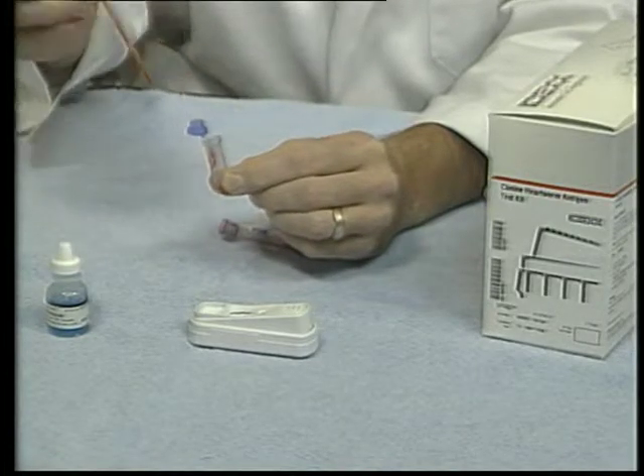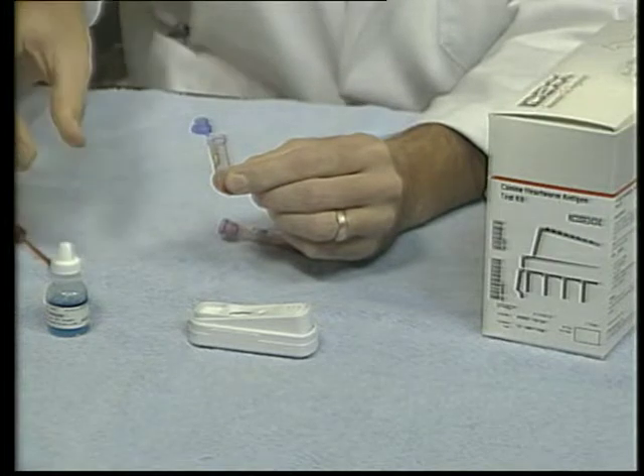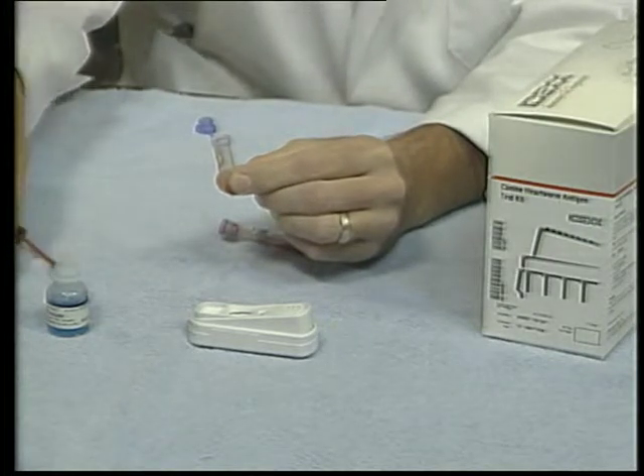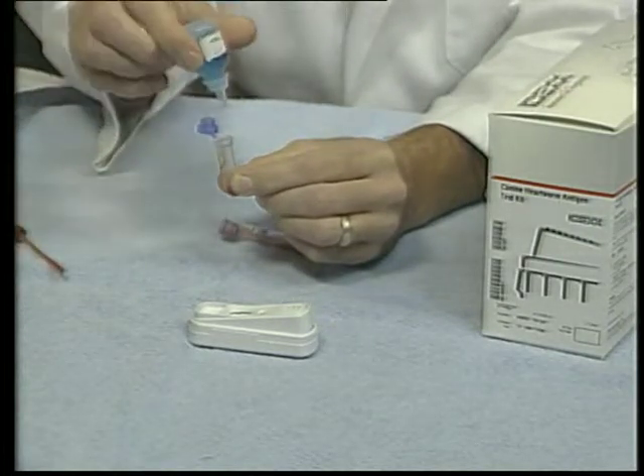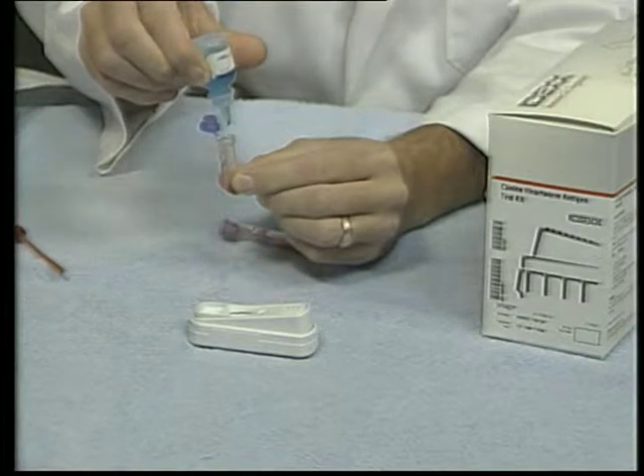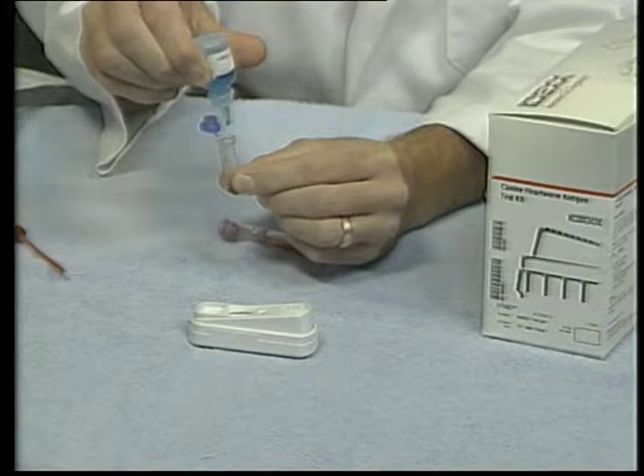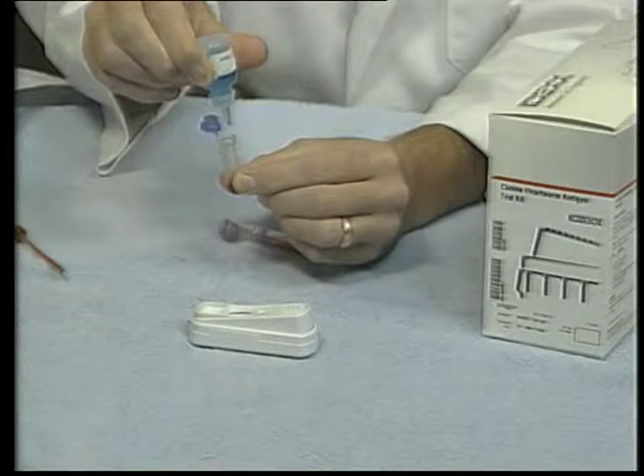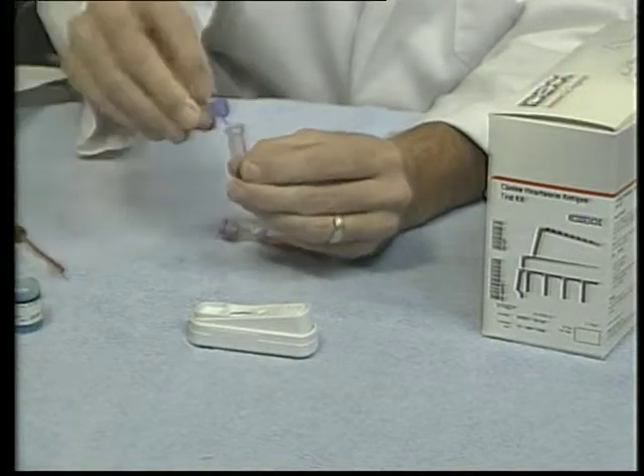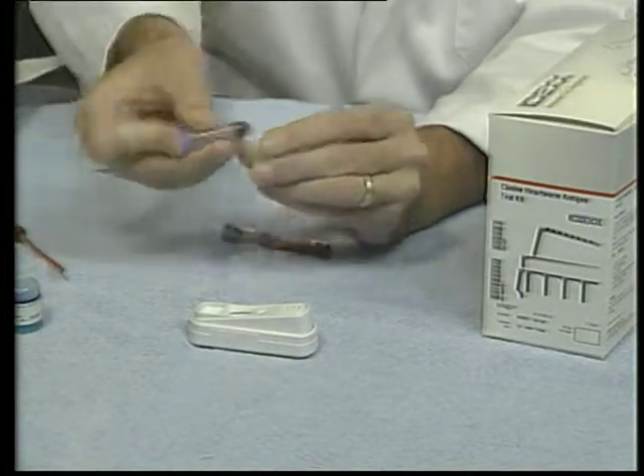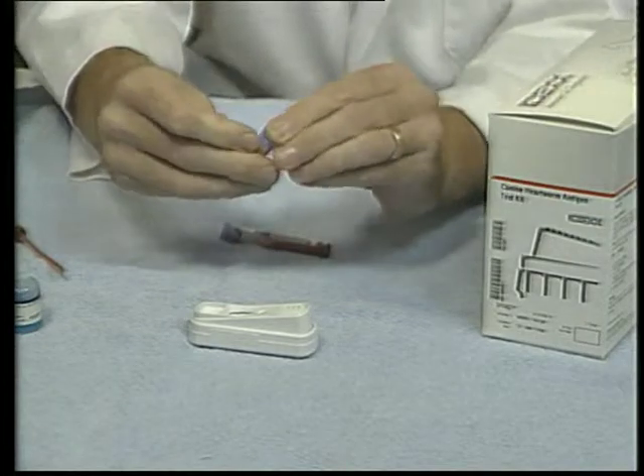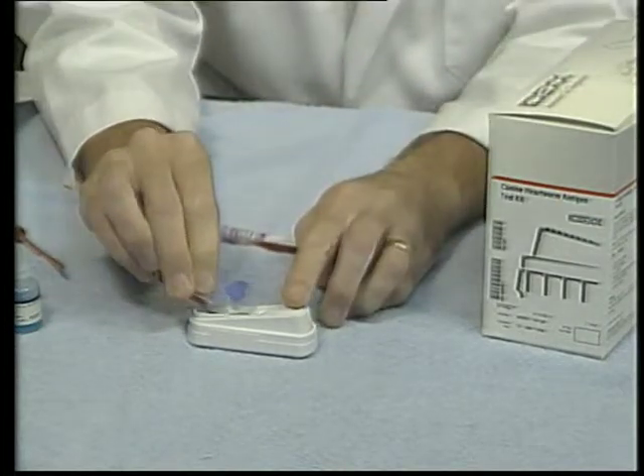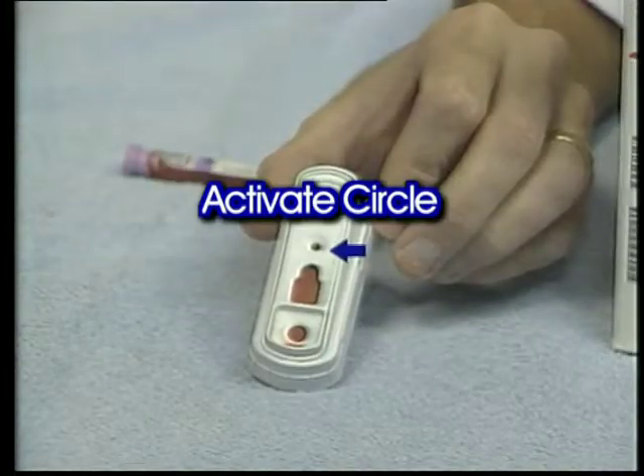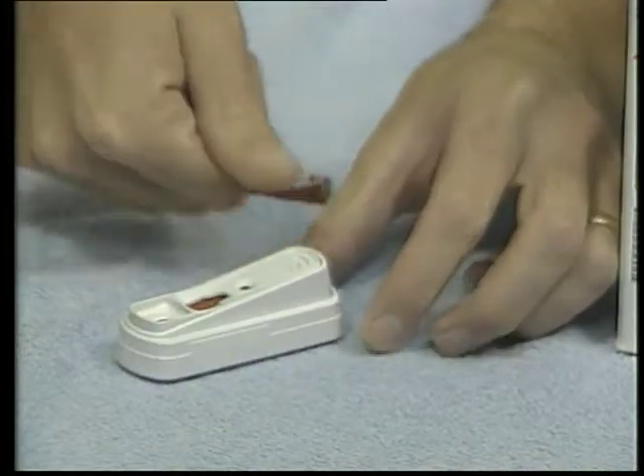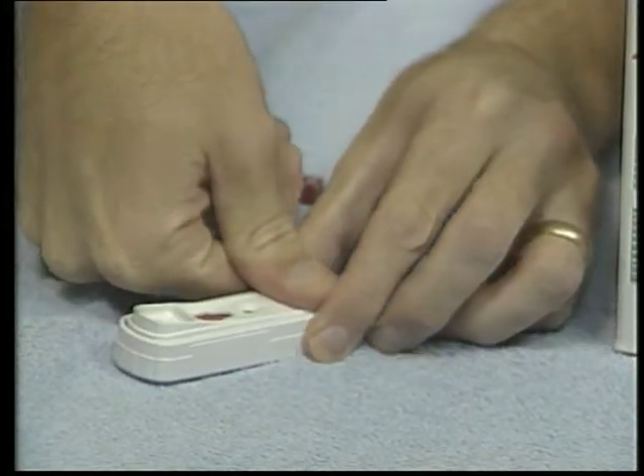Place 2 drops of serum or whole blood, as is being used here, into the sample tube. Add 5 drops of the blue conjugate and mix. Pour this solution into the sample well and wait for the solution to disseminate up to the activate circle. This will generally occur within 2 minutes. Once this has occurred, firmly press the button on the test kit until it securely clicks down.